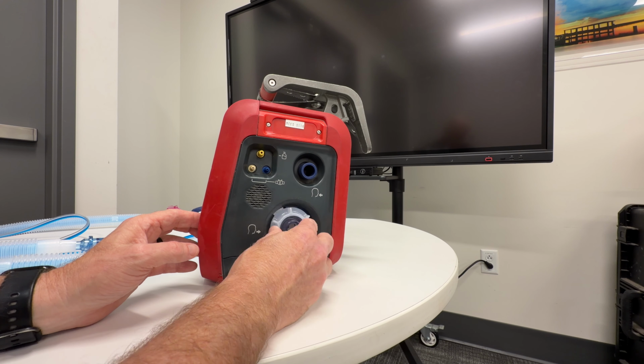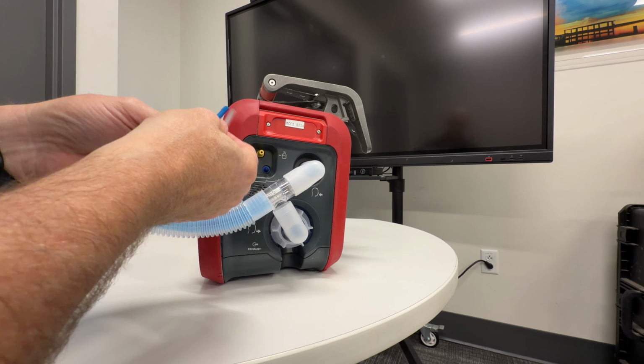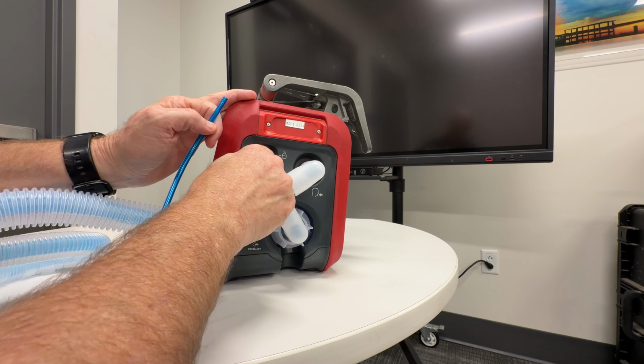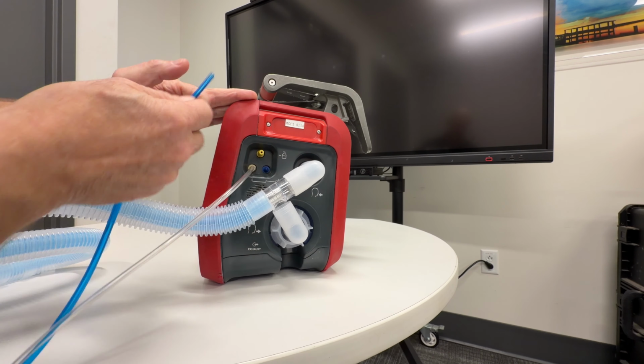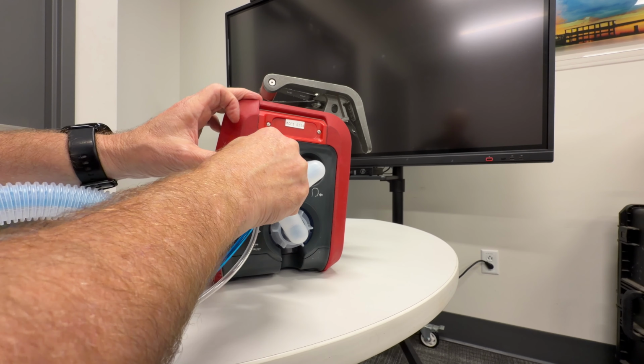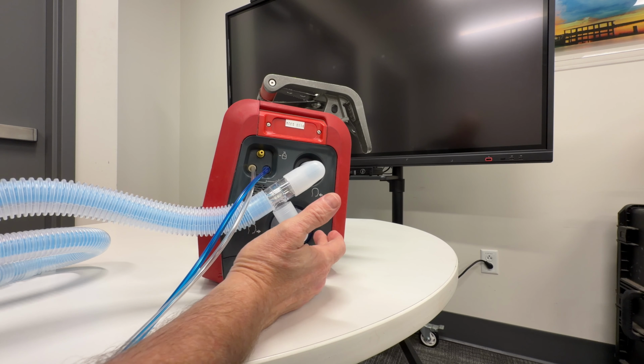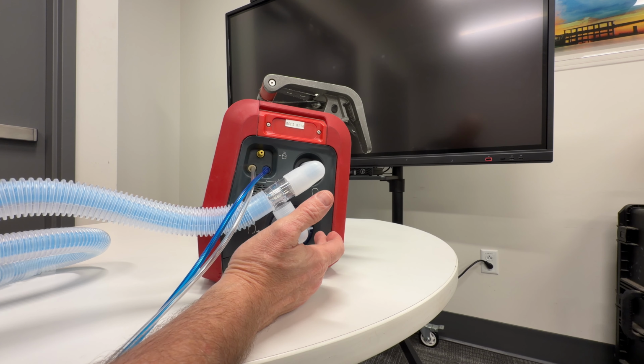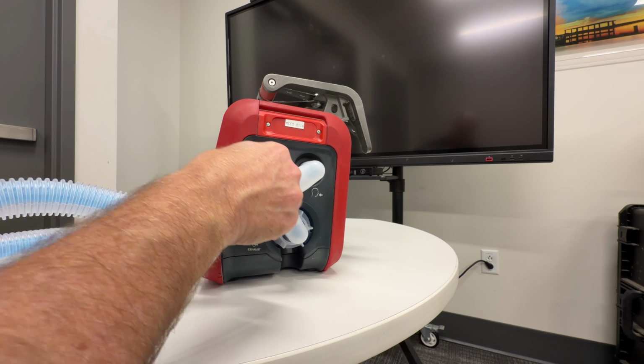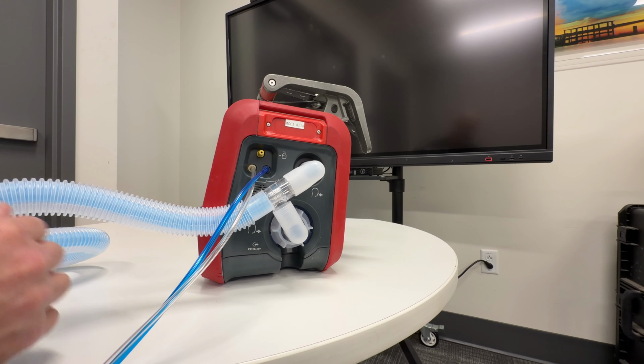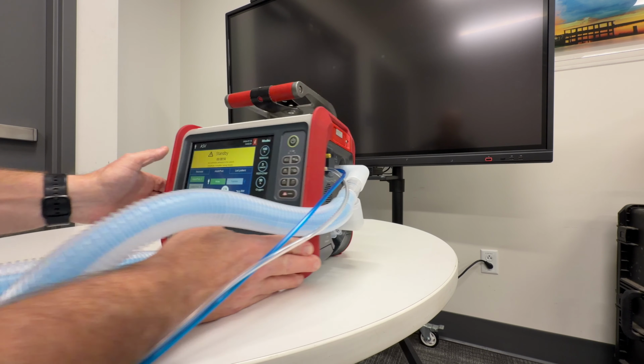At that point, you're going to take your tubing, and it's pretty simple. You're going to go blue to blue, white to white. So this is not exactly white, it's off white, but you're going to take your clear and put it on the white, and you're going to take your blue and put it on the blue. So a lot of times when people have a failed flow test, it is because either A, that diaphragm has gotten crooked on there, or they don't have these plugged up, or they have come loose. So I'm going to flip it back around.